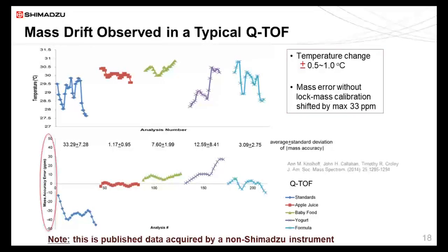And this data is extracted from the literature shown, a paper in 2014. The chart on top shows the temperature shift, and the chart on the bottom shows the mass accuracy error at the same time. And this mass accuracy error is coming from the lock mass ion. So these ions are constantly measured, and because these are the lock mass, you can observe the mass error before being corrected.